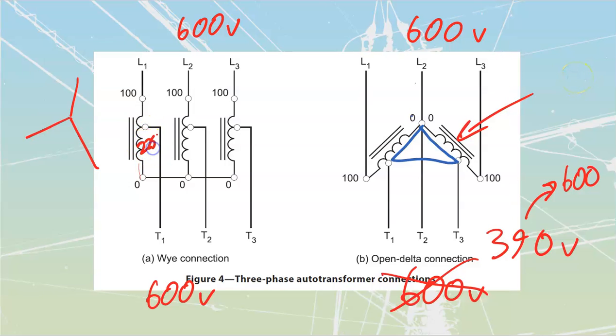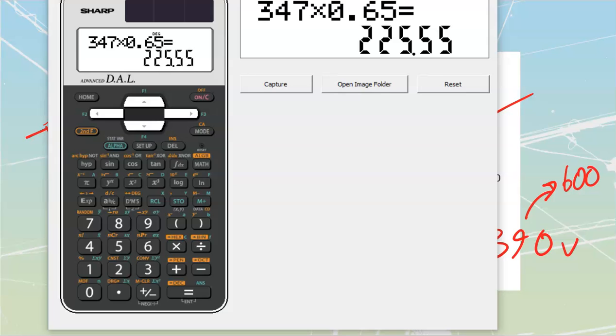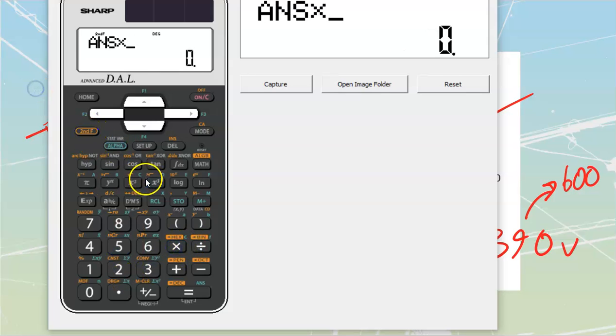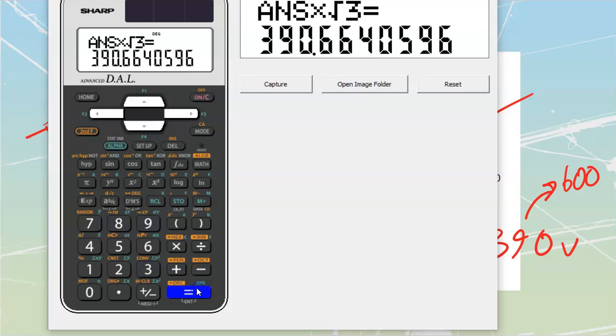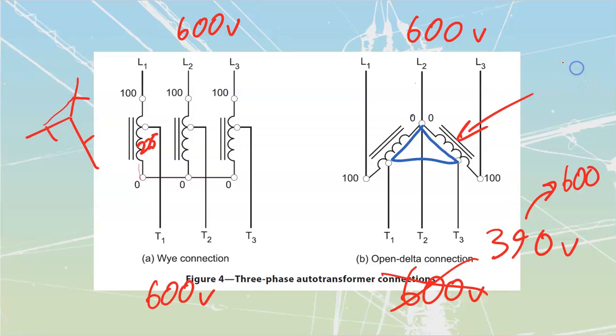So right now I'm going to be at 225 volts there, but remember that this is 225 volts that's still connected as a Y as well, and that 225 would be a phase value of voltage, which means that we should be able to get a line to line by taking that phase value and multiplying by root 3. So let's do that. Take this times root 3 over here, which gets us up to a value of 390 volts. I see that on this one as well, because now I'm going with that line to line, and that's really what this motor is connected to. Take a look, the motor is connected from line to line. We see that we would be at 390 volts starting, and then kicking that up to the 600 volts when we make that transition.